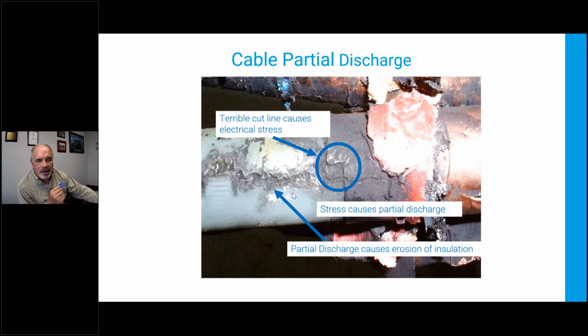Here's an example of a cable, and anybody on this screen that's a cable expert is absolutely horrified. You've got this cutback, which is terrible, and you can see the insulation's eaten away and it's flashed over. This was not caught ahead of time. This is after the fact.